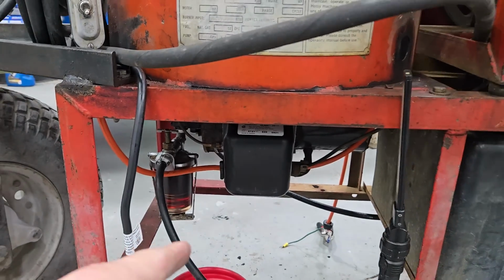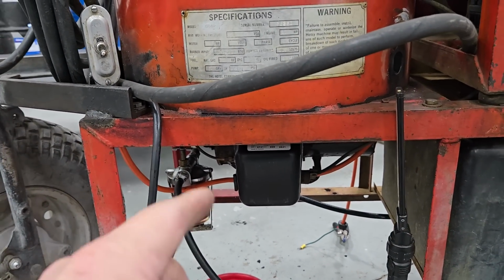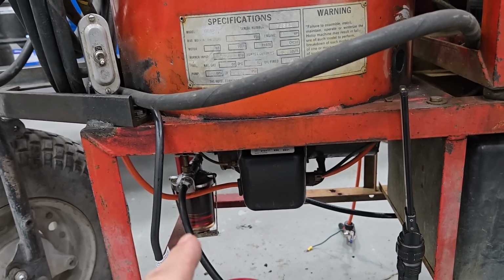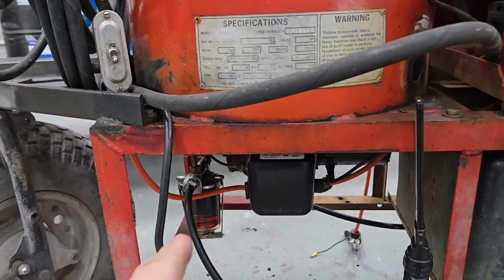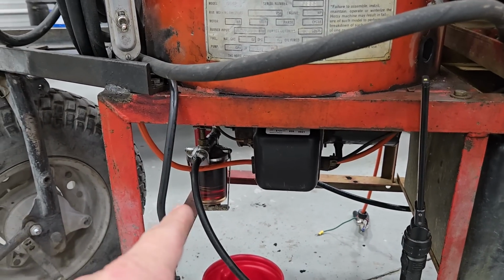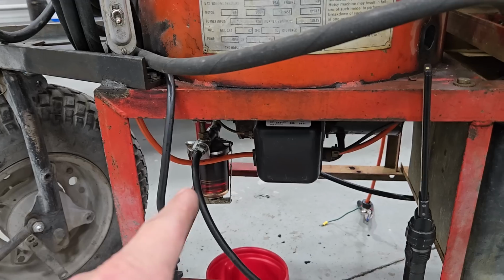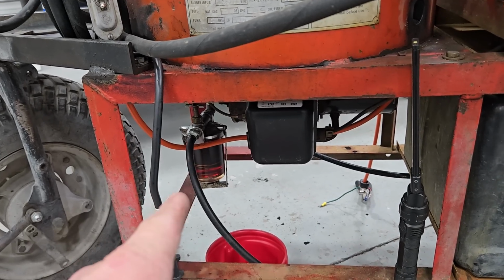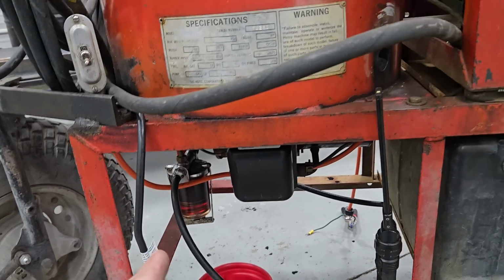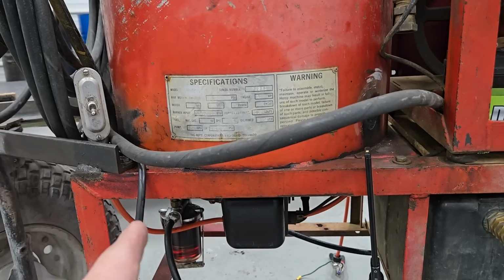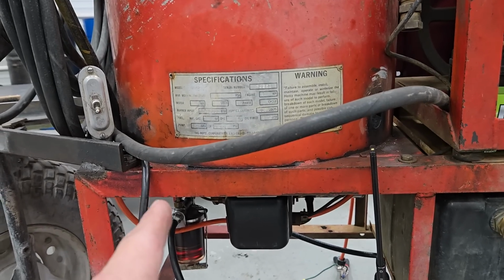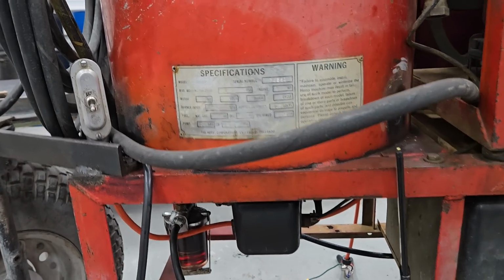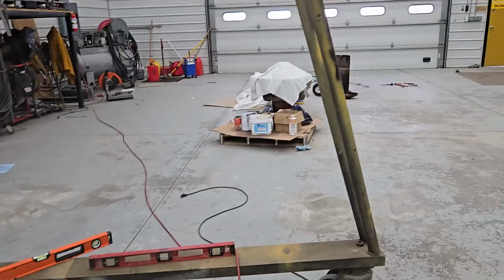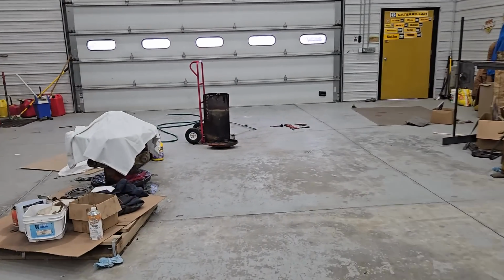As far as the burner goes, we have done absolutely nothing to that burner since 1986. No one has ever even taken the water separator filter off and cleaned it, ever. It has had nothing but number 2 off-road fuel burned in it, and that's why the coil was plugged up.